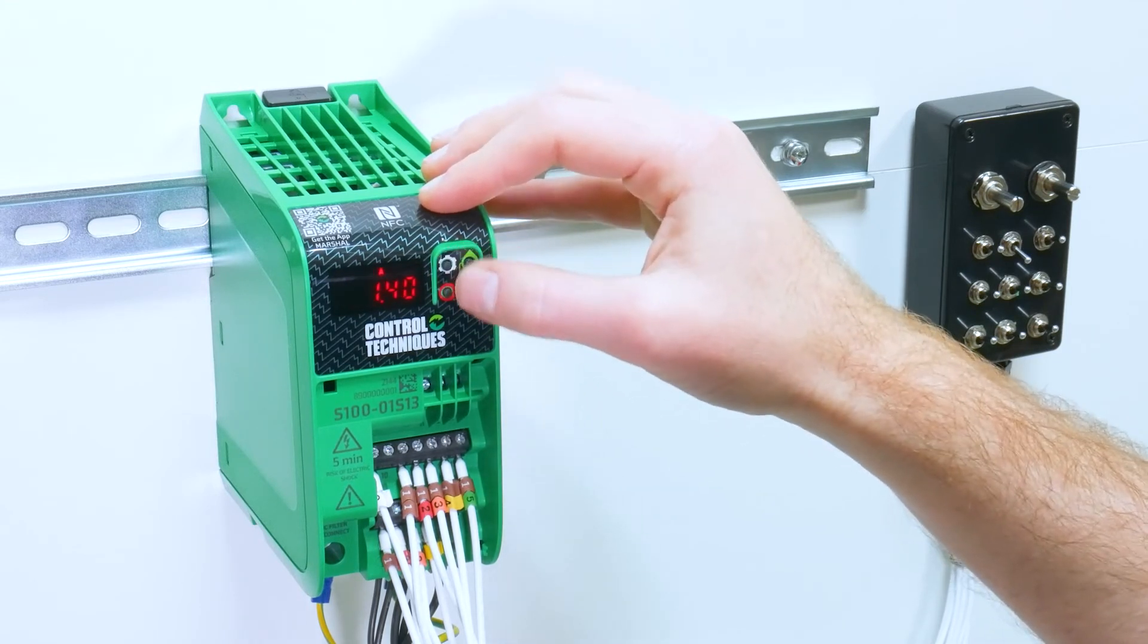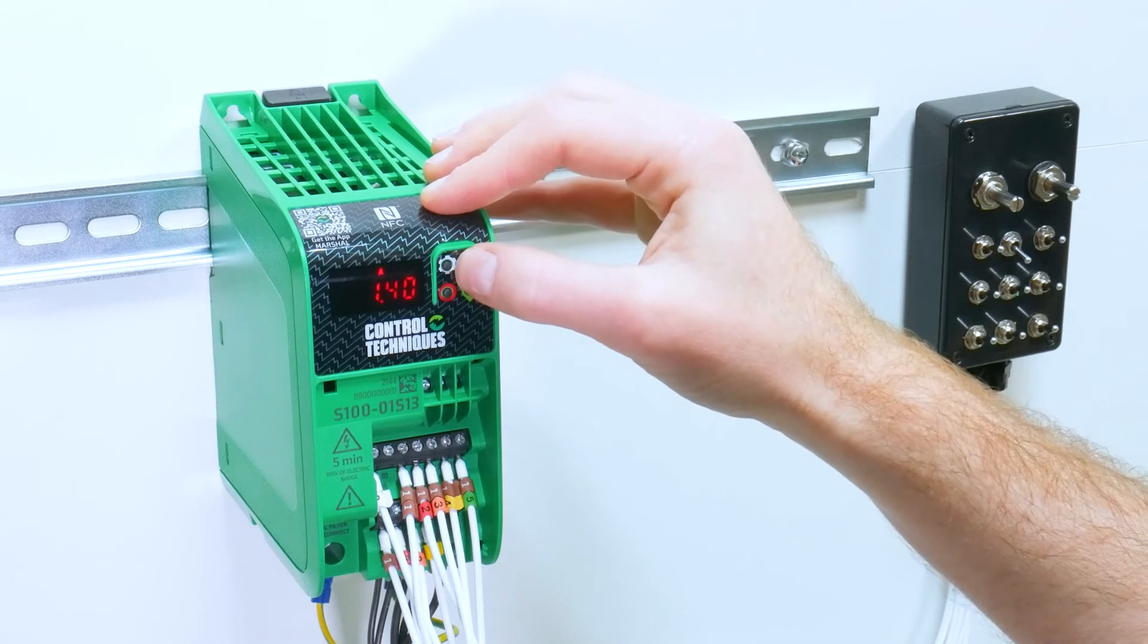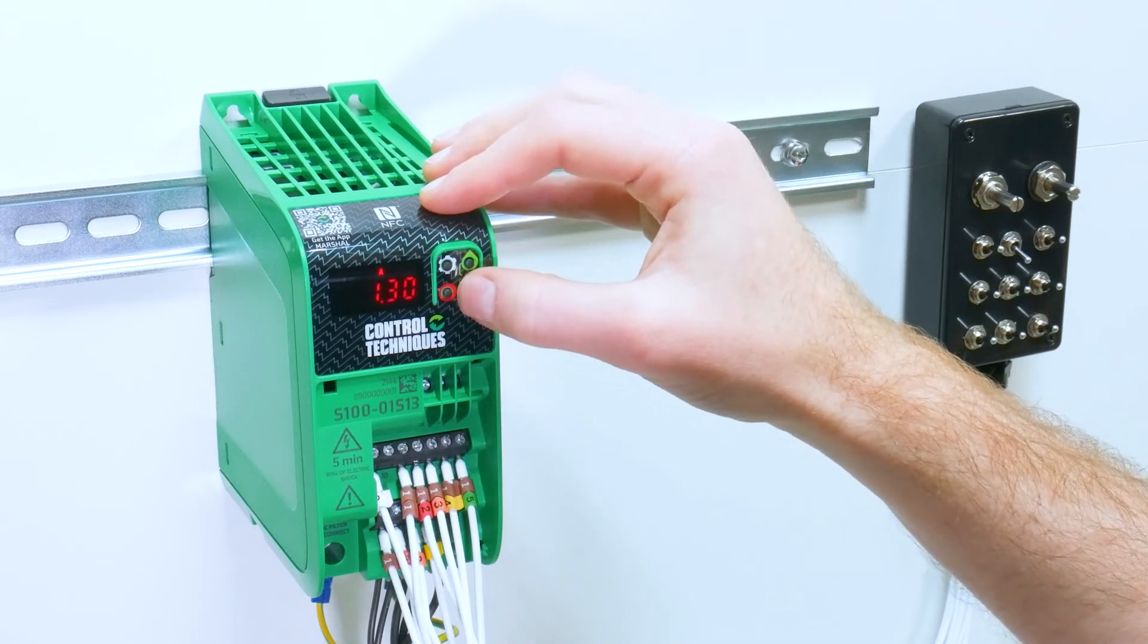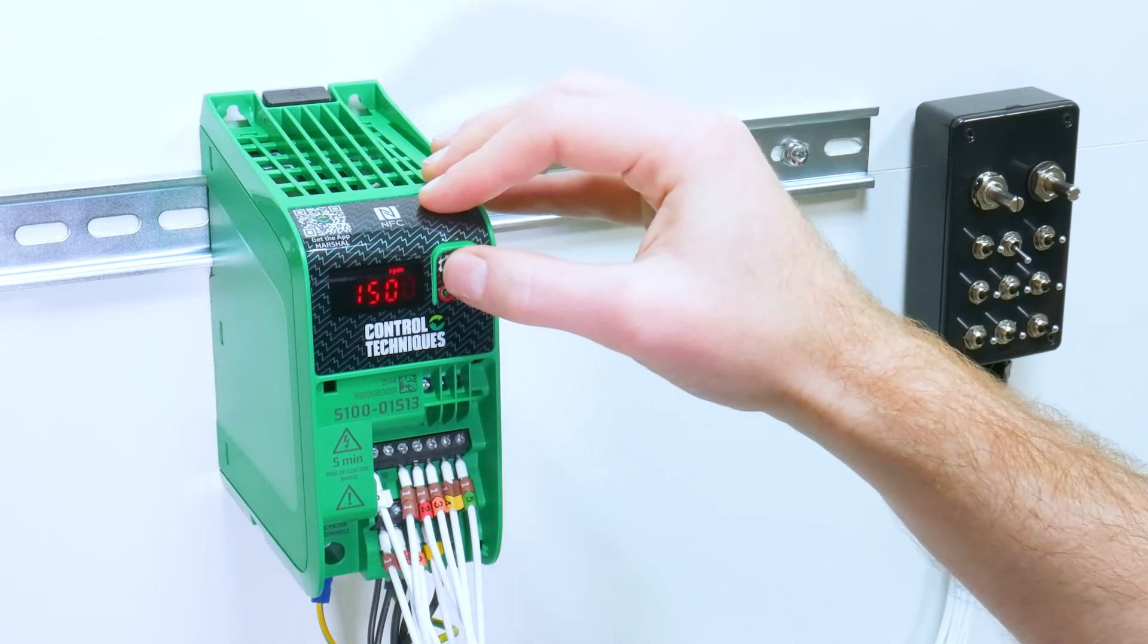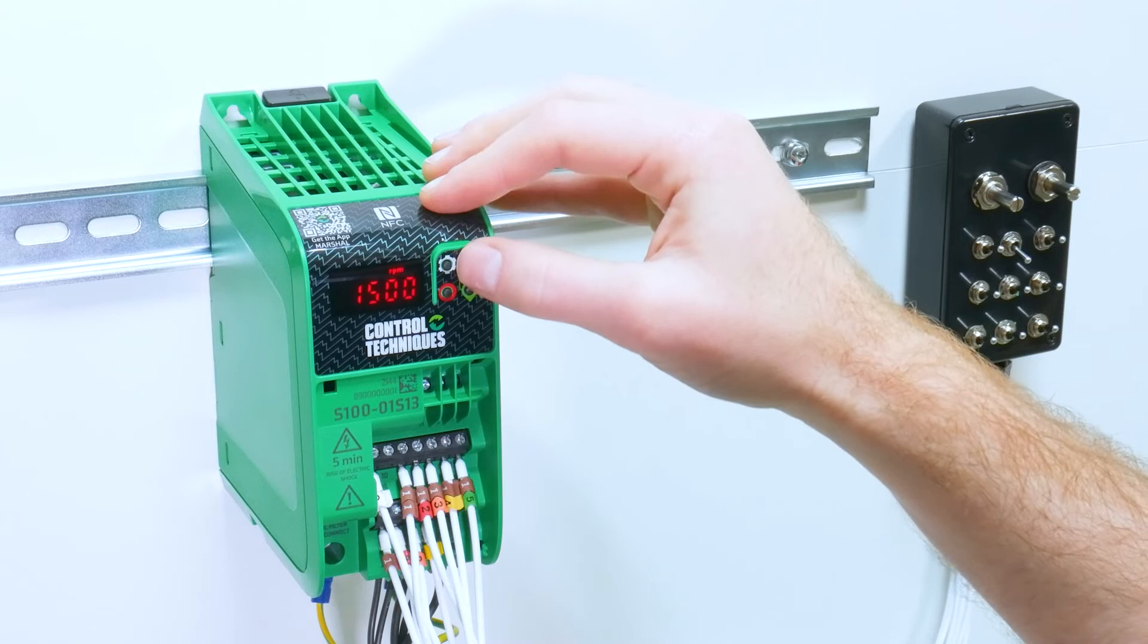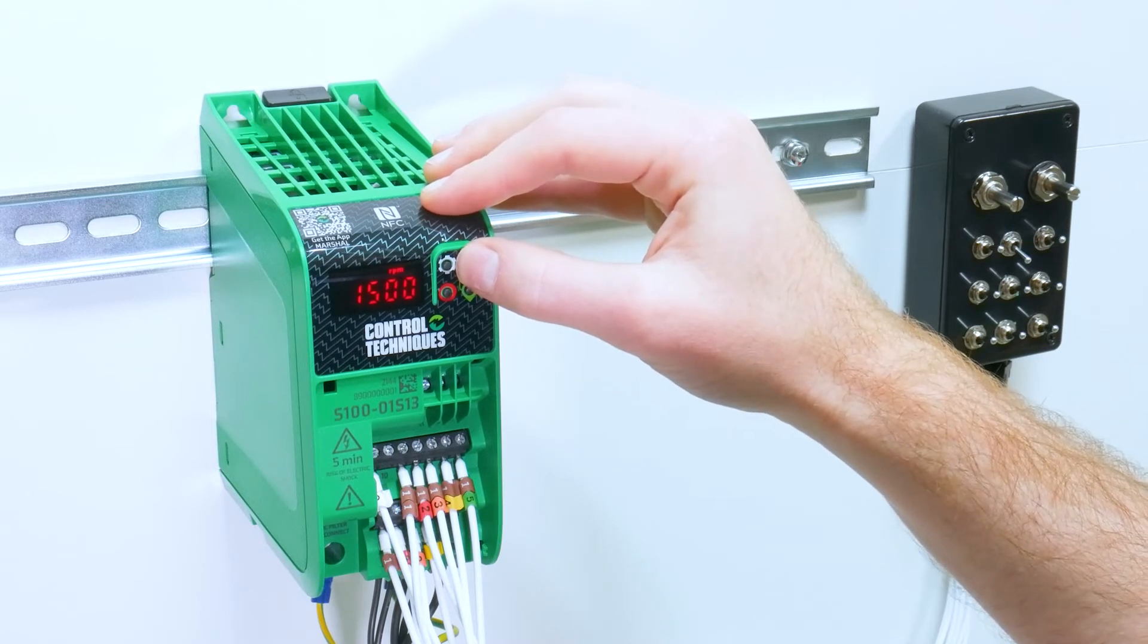Parameter six is our motor rated current. For me this is 0.7 amps. Parameter seven is our motor rated speed. I can scroll across to the hundredth digit by holding the up key.